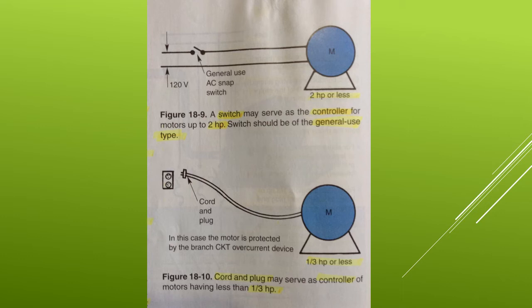Of course, the nameplate provides full load and locked rotor current ratings. If exact current values are not given in the charts, then go to the next higher current in the table to find the horsepower rating. Some controllers are rated in full load current or locked rotor current. In such cases, the horsepower equivalent is not needed.